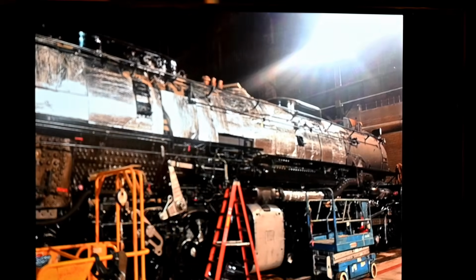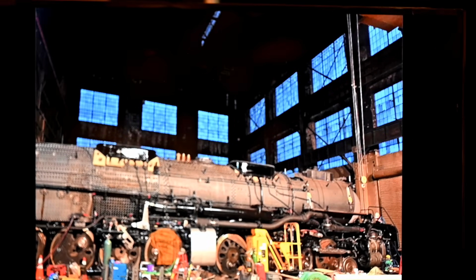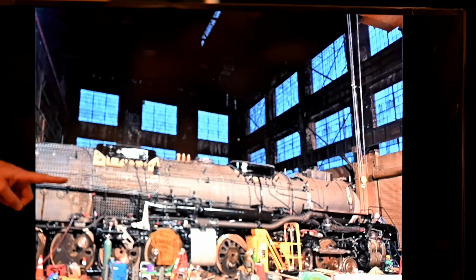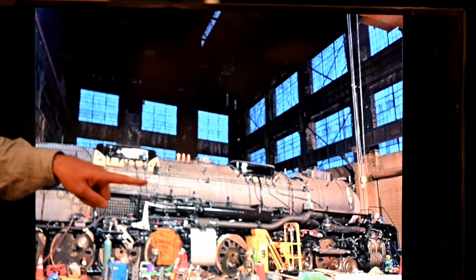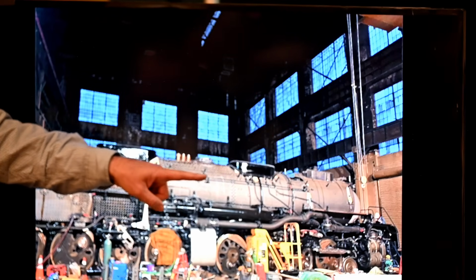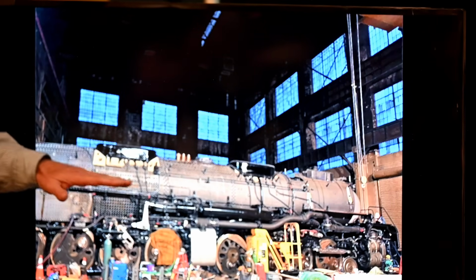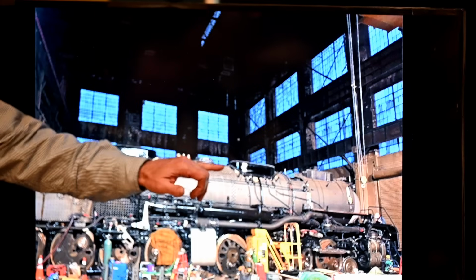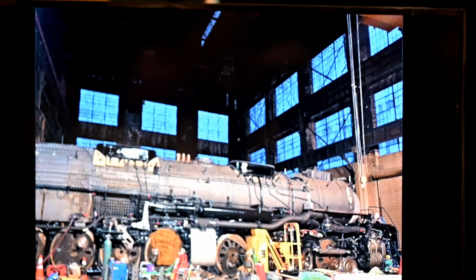Let's flip back just a couple and I'll illustrate what I mean. So what the stay bolts, there's a good one. You can see a lot of these little bumps here. Some of those are rivets. You can follow the symmetrical lines and the rows of the liners. We're looking at the outside now; we were looking at the inside a few minutes ago. Notice there's nothing on these cylindrical portions other than where they're attached from one to the other. And you've got big reinforcing plates where you penetrate the structure, so there's a dome. We can actually climb down in for inspections and work on things. And the dome is also the highest part of the boiler where the steam is collected.